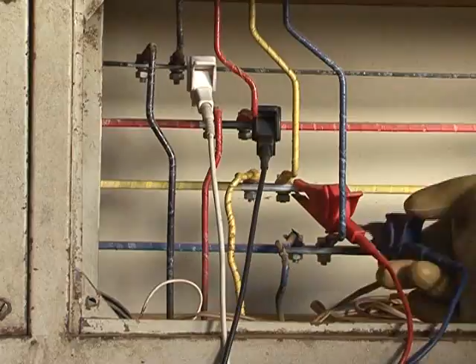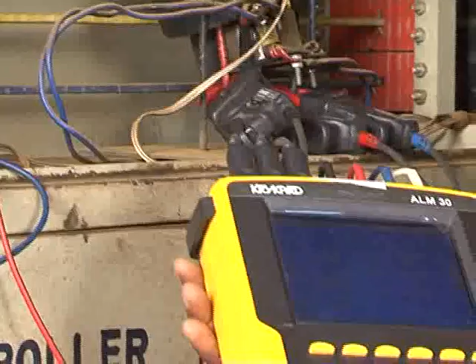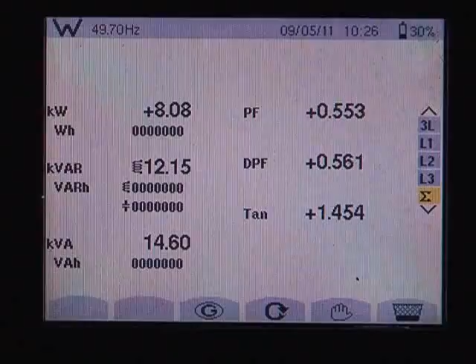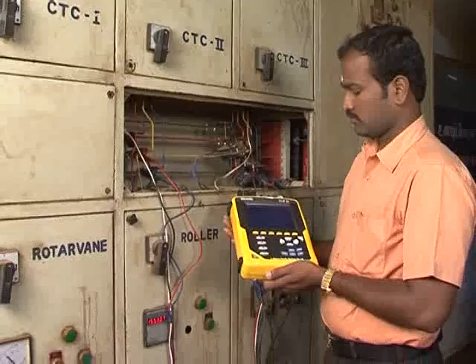To understand the proper load and capacity of the motor, it is necessary to measure two parameters: percentage loading of motors and the power factor. Simple measurements can lead to considerable saving. The equipment required for measuring is not expensive and easy to use.